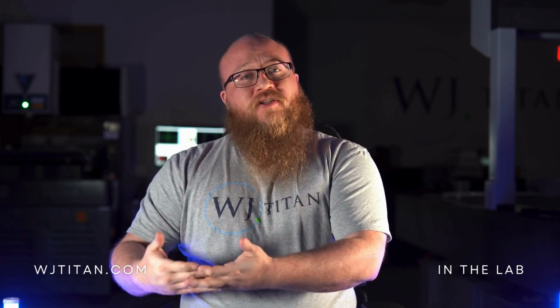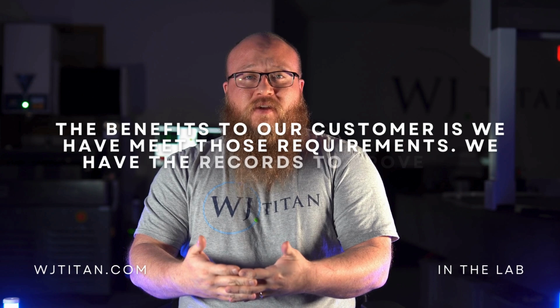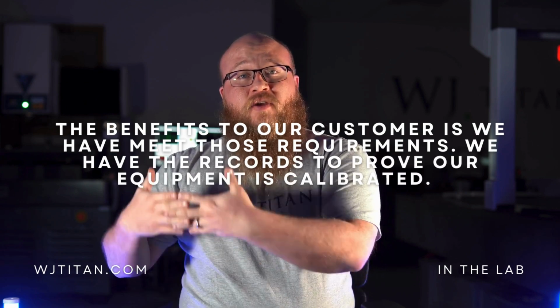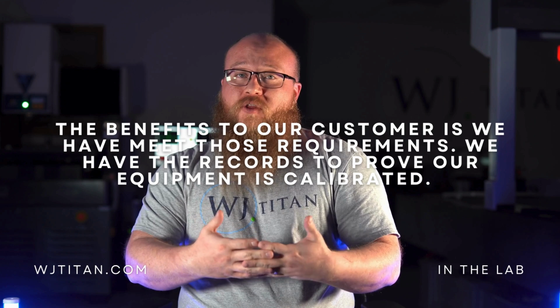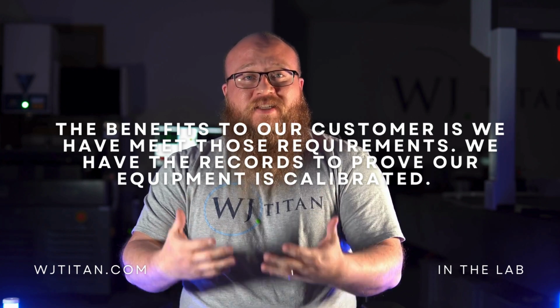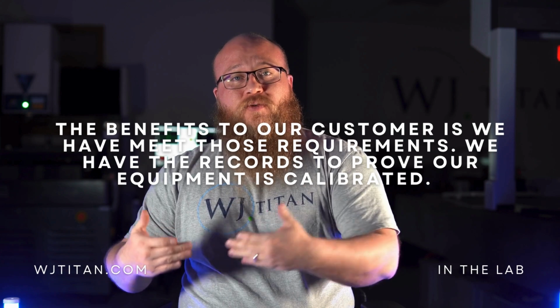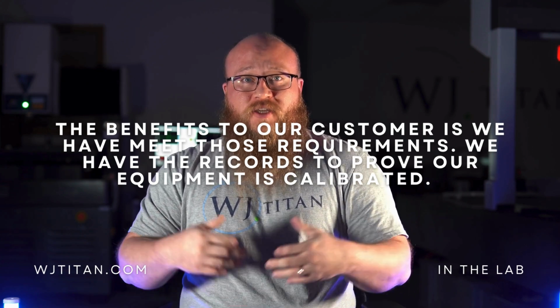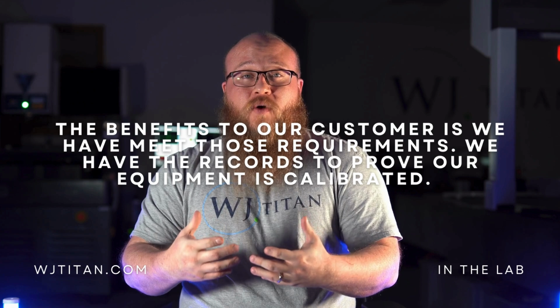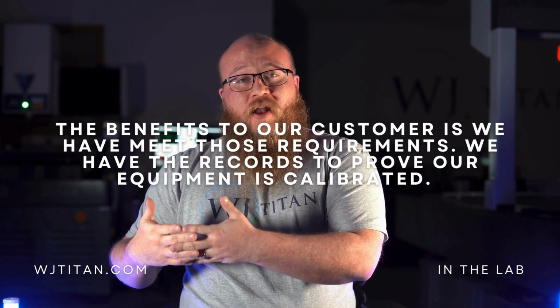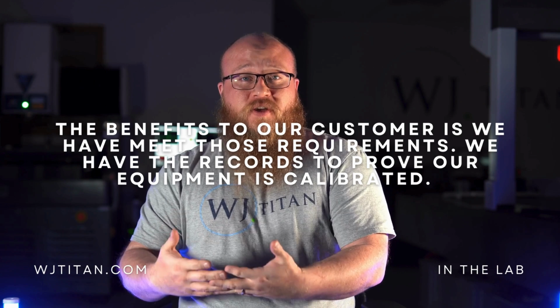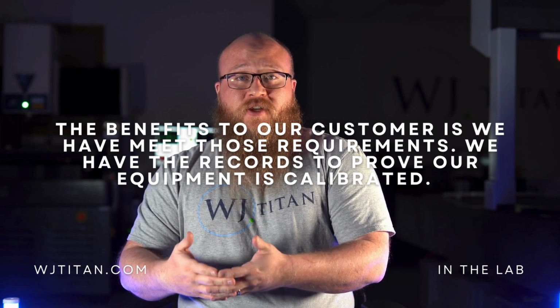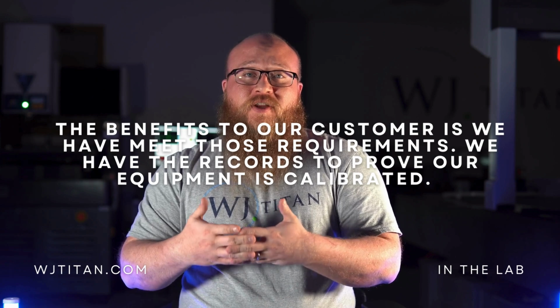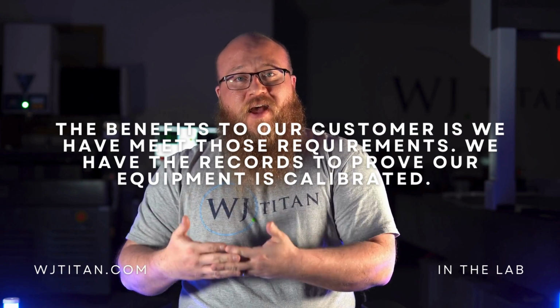So the benefit to our customers, where we say that we have a 17025 accreditation, means that we meet those requirements. We have all the records to prove that our equipment is calibrated and stays calibrated through its annual cycle, and that all of our operators and programmers meet the accreditation requirement of competency. Now, there's a small aspect of 17025 called uncertainty that also requires us to have an uncertainty budget for all of our equipment. That uncertainty budget lets us determine and evaluate what our potential error is in all of our measurements. That's something else that we're required to communicate to our customers.